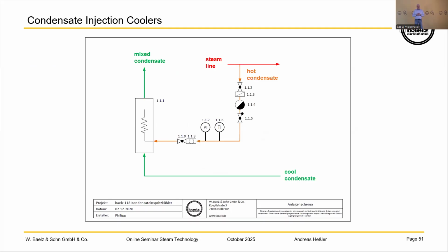You will go into the pipes with the hot steam condensate, and this hot steam condensate will cool down by the cold condensate, and the cold condensate will be heated up. So when you put it together, the temperature difference is not so big. You have then a mixture of the hot and cold condensate without hammering, without noise. And it's a very good solution when you have to put hot condensate into cold condensate.